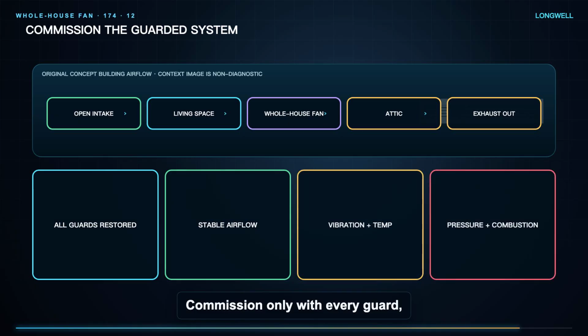Commission only with every guard, cover, shutter, and access panel restored. Reopen the specified intakes, verify smooth start and stable airflow, check vibration, noise, temperature, controls, and shutdown, then confirm building pressure and combustion safety where applicable. Record the final configuration and measured observations.